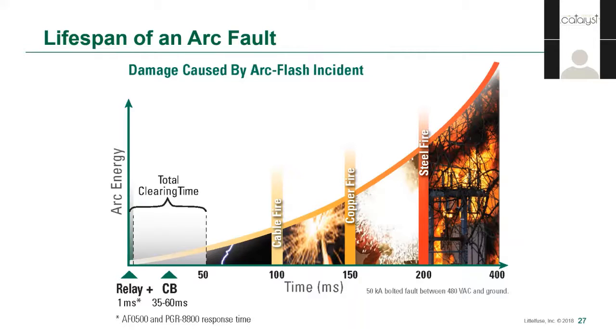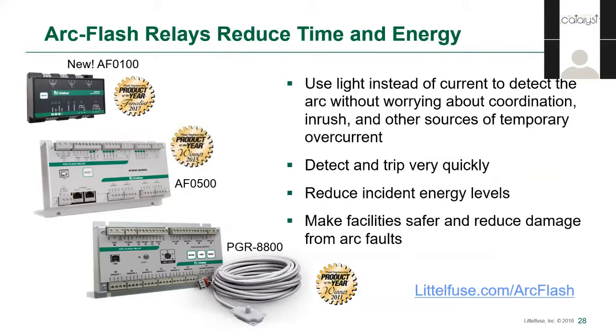With a detection and response time of less than 1 millisecond, the real limiting factor is the circuit breaker being used and how well it's maintained. Even with that factored in, a typical circuit breaker time is 35 to 60 milliseconds, which still puts us well below the typical time needed for a cable to catch fire in the event of a 50 kA arc. Note that within 200 milliseconds, steel would catch fire — and to put that into perspective, the blink of an eye takes about 300 milliseconds. This slide shows the Littelfuse family of arc flash relays, all designed to use light instead of current to detect an arc without worrying about various sources of temporary overcurrents. Each of these products detects and trips connected breakers quickly, and can be designed into new equipment or retrofitted into existing equipment, reducing the potential energy level in the system and making facilities safer.